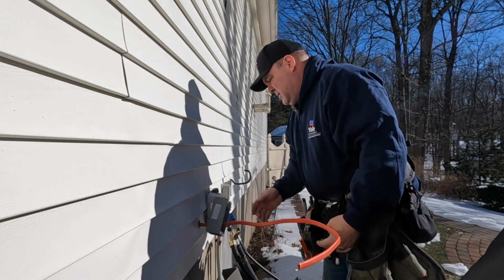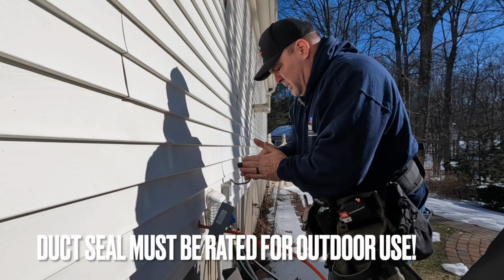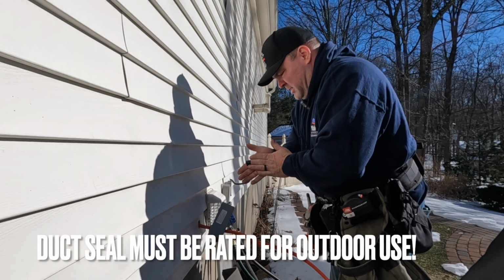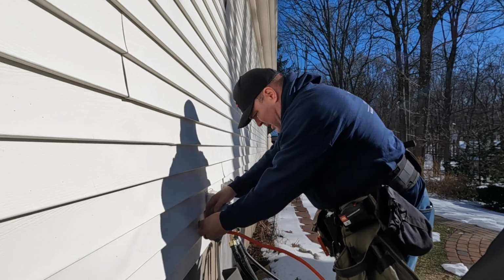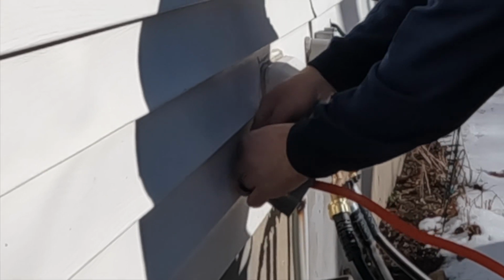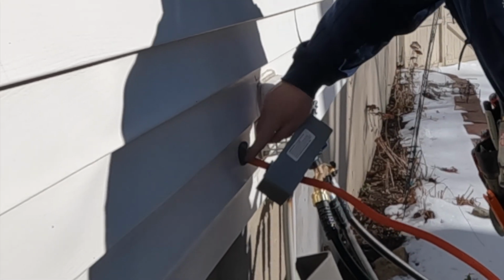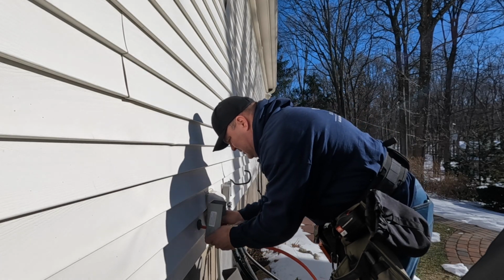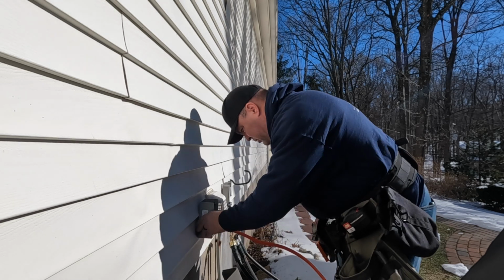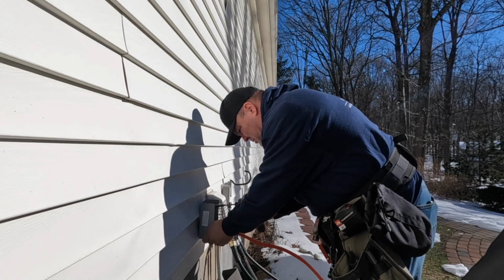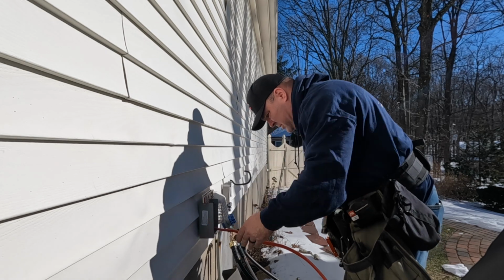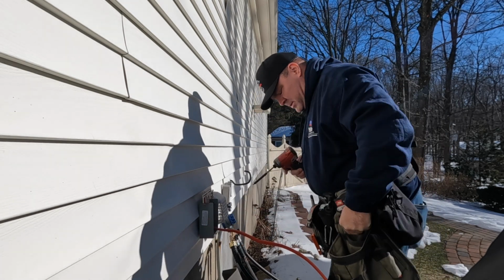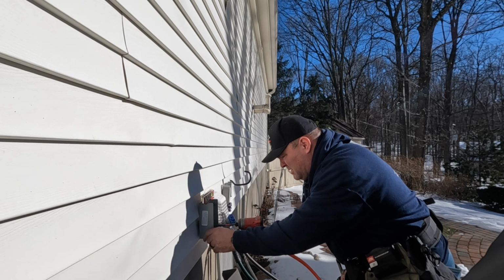All right. Now what we want to do is we want to get this duct seal on the top, just like that, around the wire, around the cable, so that when I push this in, it's going to be completely covered just like that. Of course, you want to make sure that it's level. Good workmanship, right?